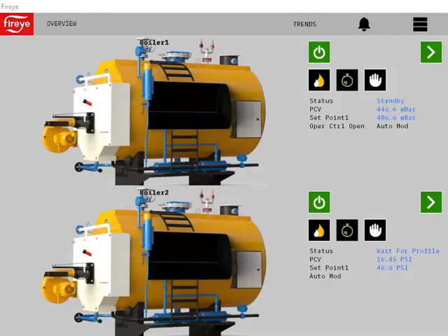In the previous tuition video, we created a rising analog alarm for all NXF4000s in the project. A sensor 1 high alarm triggers at 600 millibar. However, in the current project, boiler 1 sensor is set to millibar, while boiler 2 sensor is in PSI. Obviously, boiler 2 can never reach 600 PSI, so the sensor 1 high alarm will never trigger. This can be solved by the use of custom variables.